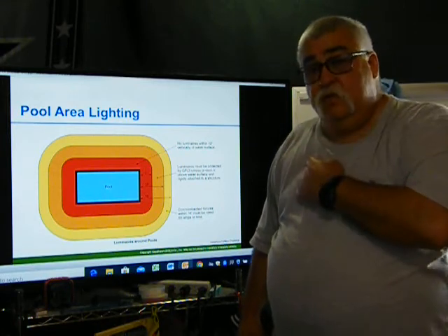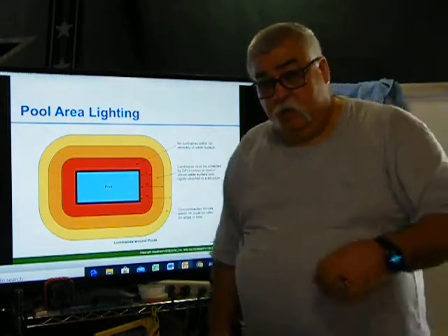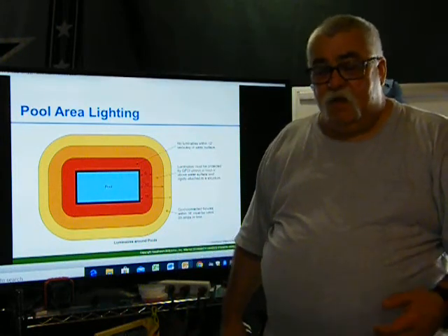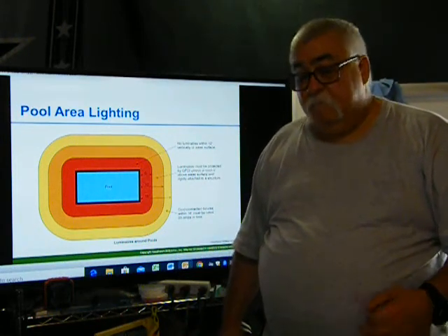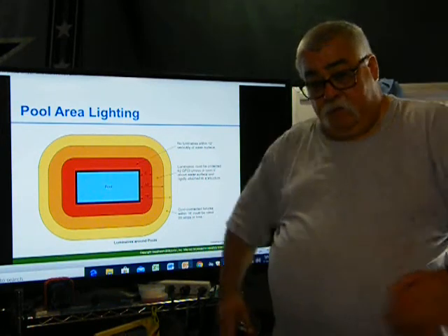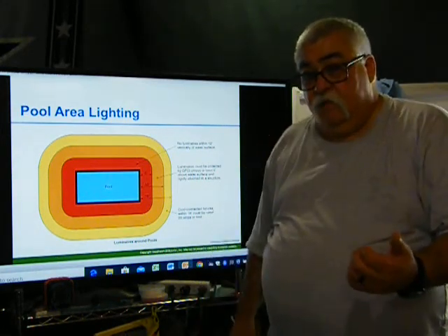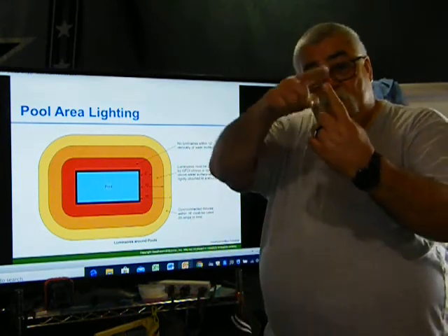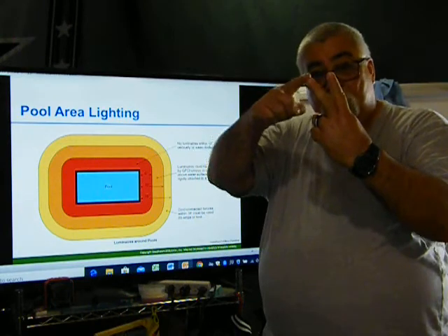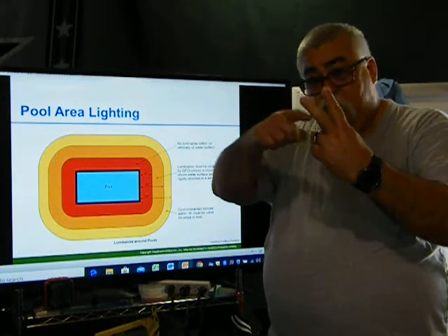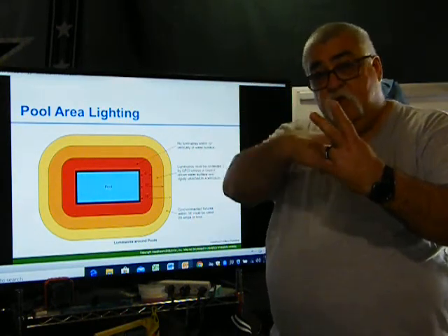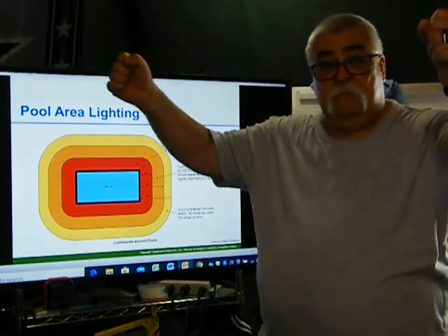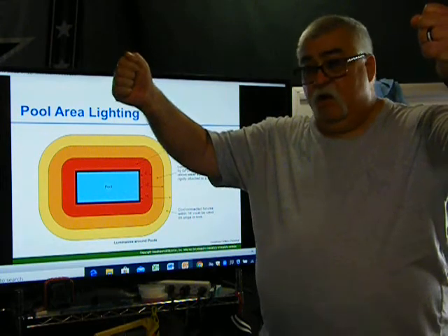Okay, but why does the GFI not trip? Well, a GFI is supposed to trip at 6 milliamps. And guess what? If I got 7 milliamps, or 10 milliamps, or 15 milliamps, or 20 milliamps, it's not enough to kill you. It can paralyze your muscles. Not enough to kill you, but the GFI will not trip. Why? Because if I got 10 milliamps on the hot, I got 10 milliamps on the neutral, because whatever's coming on that hot is going back on the neutral, going back to the GFI. GFI says, hey, I got 10 milliamps, I got 10 milliamps. My circuit is balanced, stay on.